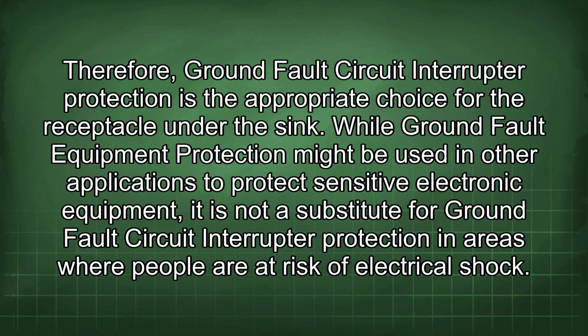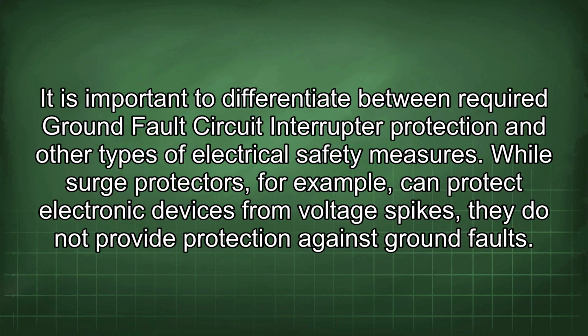Therefore, ground fault circuit interrupter protection is the appropriate choice for the receptacle under the sink. While ground fault equipment protection might be used in other applications to protect sensitive electronic equipment, it is not a substitute for ground fault circuit interrupter protection in areas where people are at risk of electrical shock. It is important to differentiate between required ground fault circuit interrupter protection and other types of electrical safety measures.